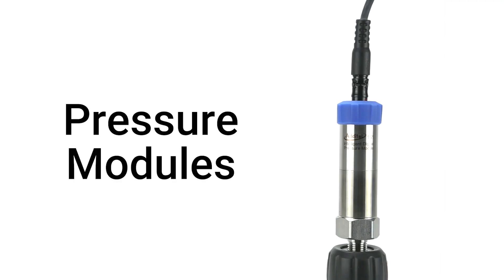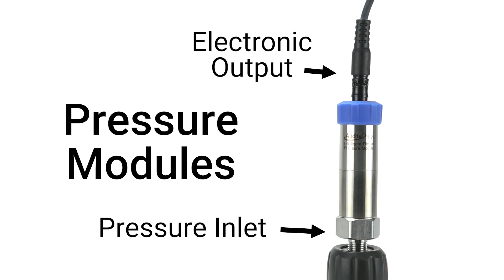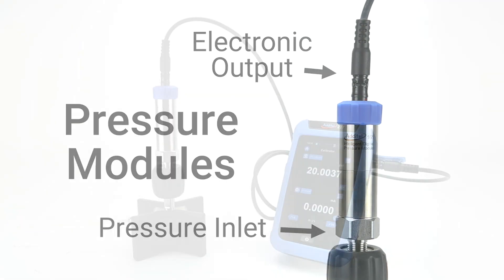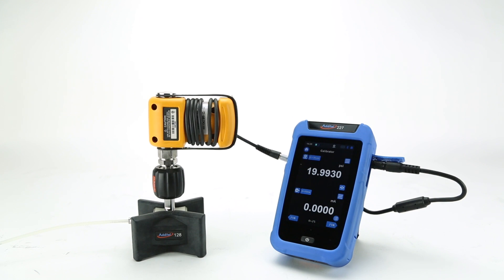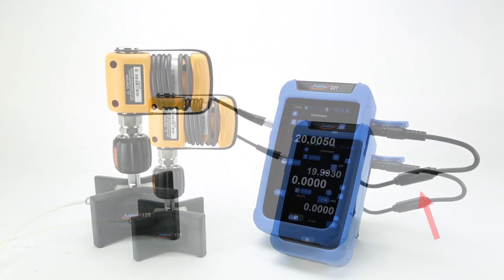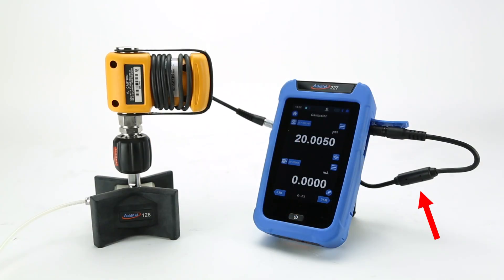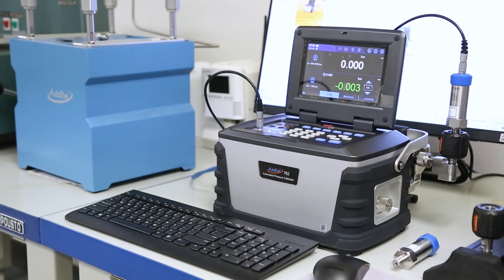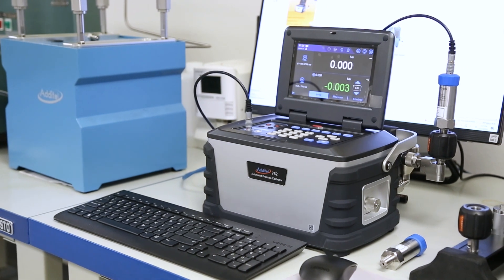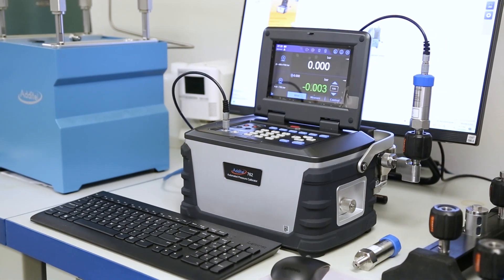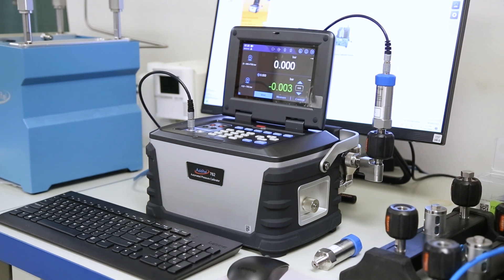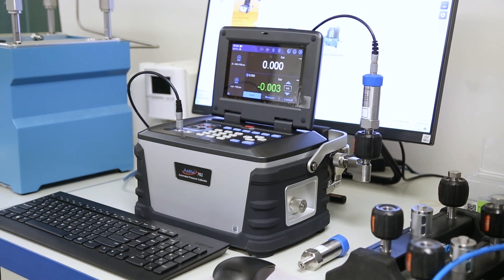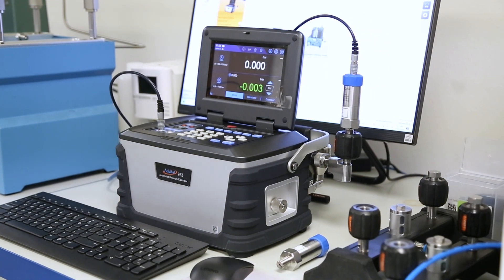Pressure modules convert a pressure signal into an electrical signal to be read by an external device or software. These signals are often proprietary to the manufacturer of the module and require a specific cable to read the signal. High accuracy pressure modules are often used as pressure references in calibration, since their electronic output can be easily read and recorded by lab software or field calibrators.